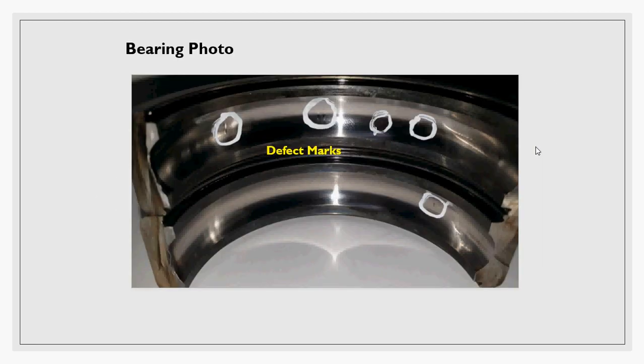After we replaced the bearing, we inspected it and found the bearing fault. As you can see in this white ring, there are tiny marks — this is an indication of false brinelling and these are your defect marks. They look tiny and you could leave the bearing to run for a while at this condition, but predicting the progression and deterioration of this fault is really very hard.